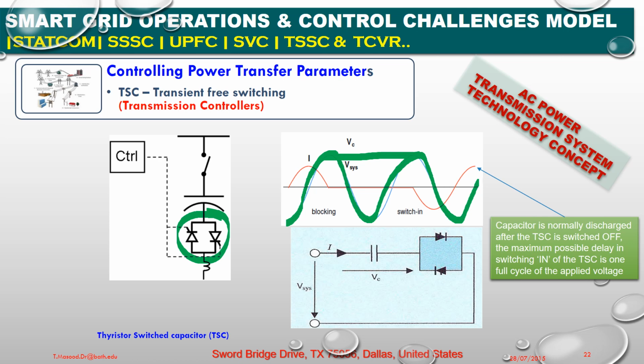Basically, the switching control in the TSC principle: once each capacitor is charged to either the positive or negative system peak voltage, it is possible to switch any or all capacitors on and off for any integral number of half cycles without transient.